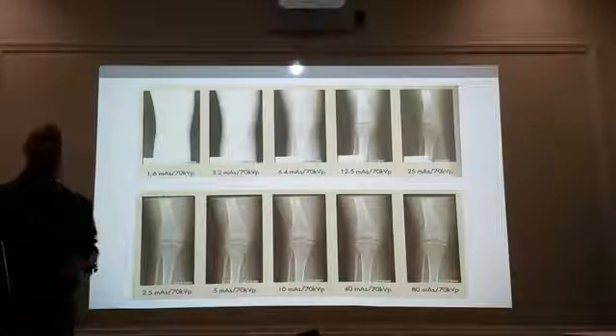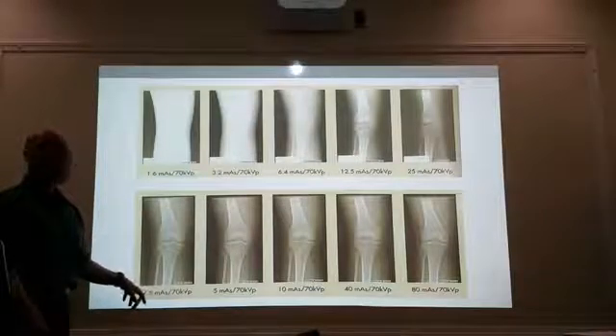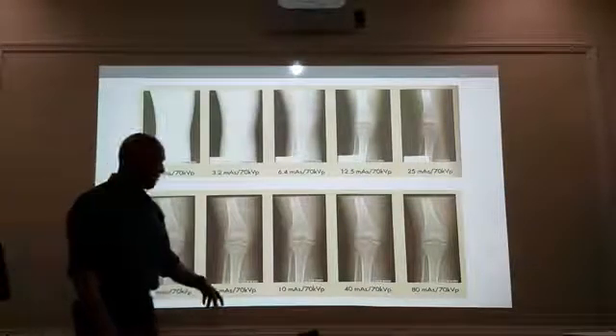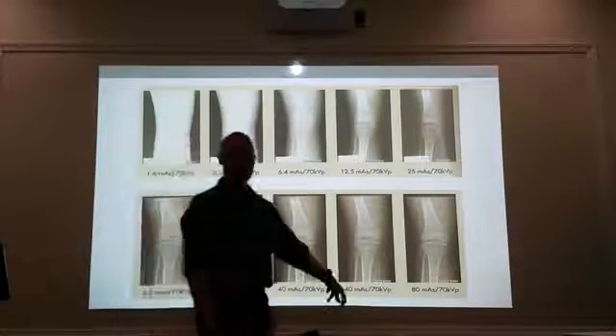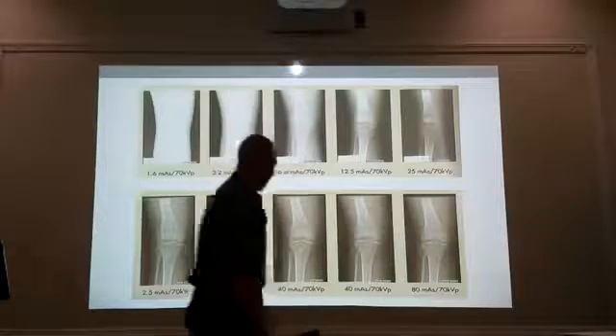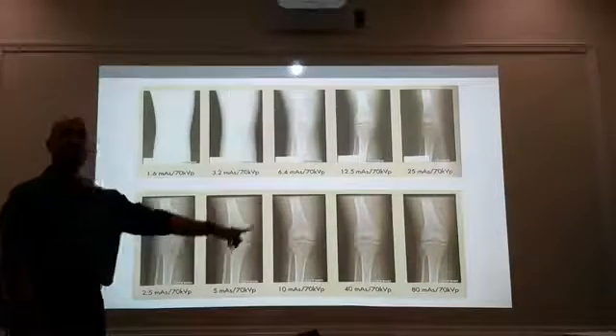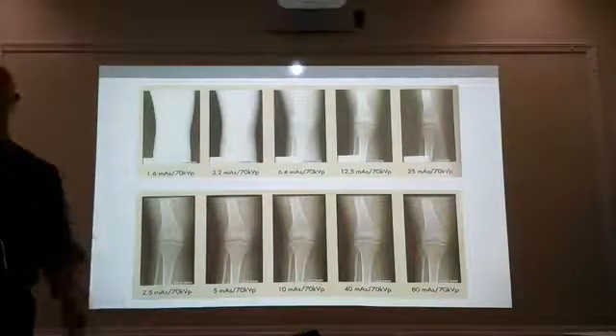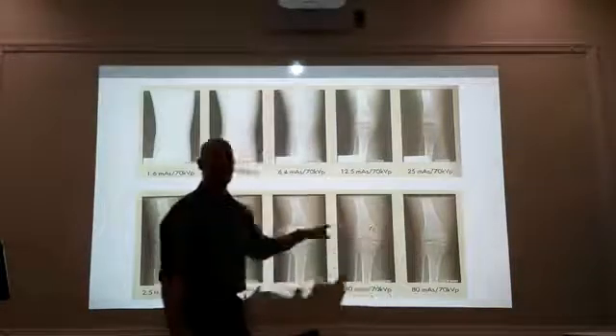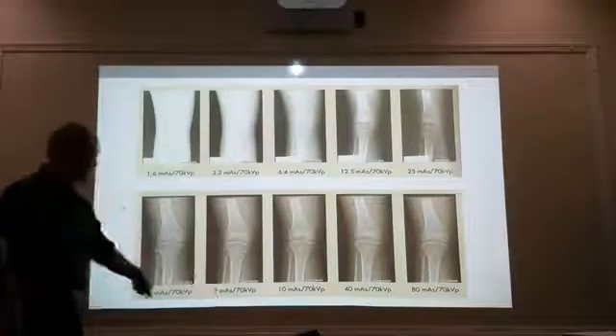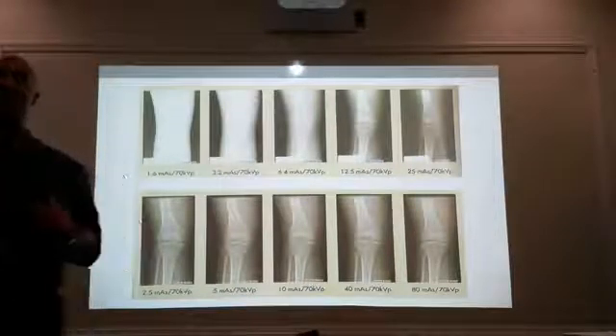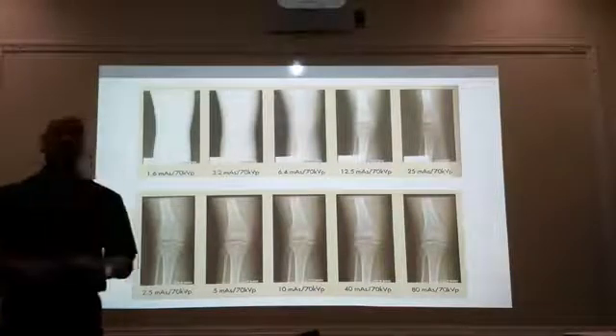Here is the same study with computerized radiography. At 2.5 mAs it looks good. We doubled it to 5 — looks the same. We doubled to 10 mAs, then 40 mAs, then 80 mAs. We went from 2.5 to 80 — that's almost 35 times the patient exposure. We could be killing our patients and not know it because the images look good every time. Your 80 mAs image looks just as good as your 2.5 mAs image. So it is our job — as quality control technologists and as the people shooting the X-rays — to make sure technical factors are set appropriately.